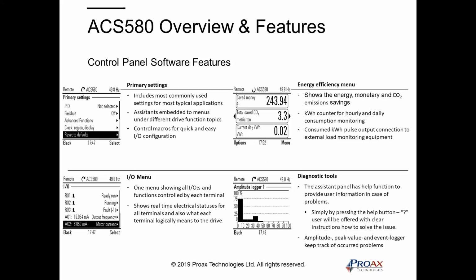From the diagnosis tools standpoint, there is a question mark button on the keypad that helps you see what's going on with the drive. These items are compared between 550 and 580 a lot. For example, if you have a fault on 550, it shows you what the fault is, but here it shows you the possibilities of the fault. You can see amplitude, peak value, event logger, and also track the occurred problem. This is very important, so you can see what happened.